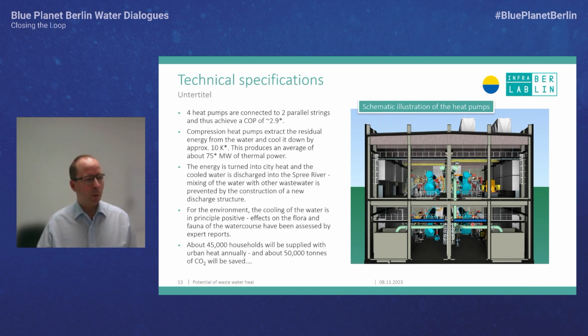Let's say we build a completely new building to implement 4 different heat pump units. Each has a thermal capacity of around 18 megawatts with around 18 tons of refrigerant. The units will be connected so that we have one string on each side of the building, each string parallel, but there will be 2 in one row. The corresponding COP at our design point is close to 3. It will be a little lower during cold winters and a little higher during hot summers, due to the lower temperature difference between the heat source and the final heat.